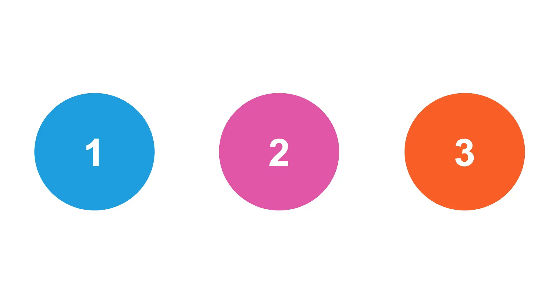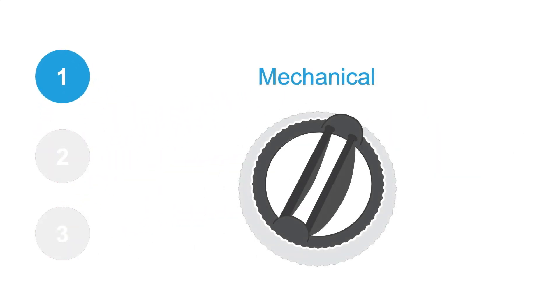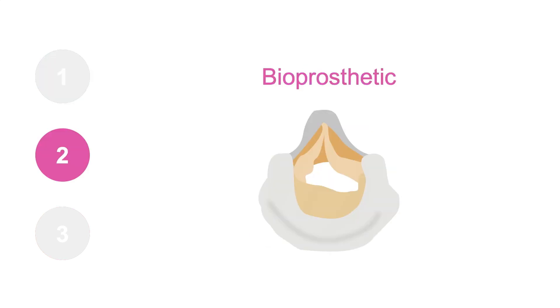Broadly speaking, prosthetic heart valves are divided into three groups. The first group is mechanical valves, made exclusively of synthetic materials. The second group consists of bioprosthetic valves and includes stented, stentless and percutaneous ones.